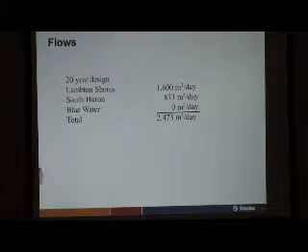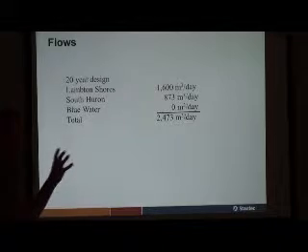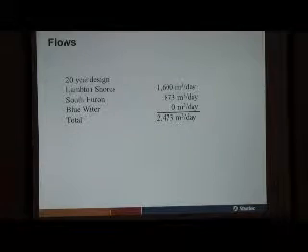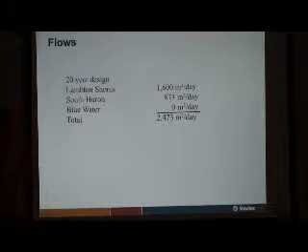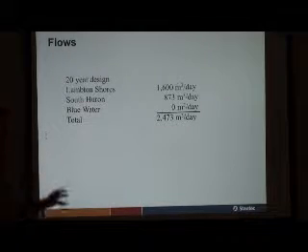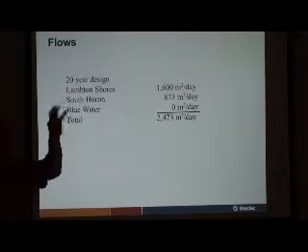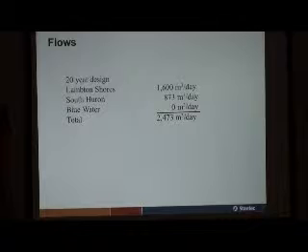Now again, we also took a look at the flows and at the actual design loading flows for the plant. The current plant that was tendered had a design capacity of about 4,600 cubic meters a day. We took a look at what the 20-year design flows would actually be, using existing flows plus the current flows that are committed plus growth for 20 years.